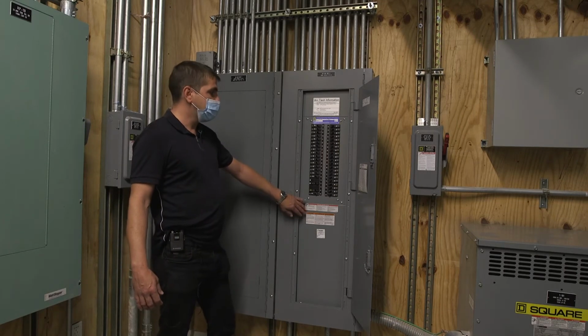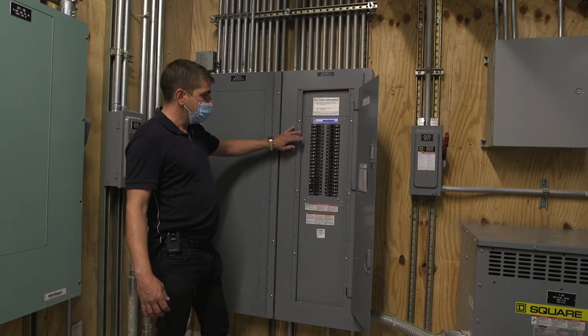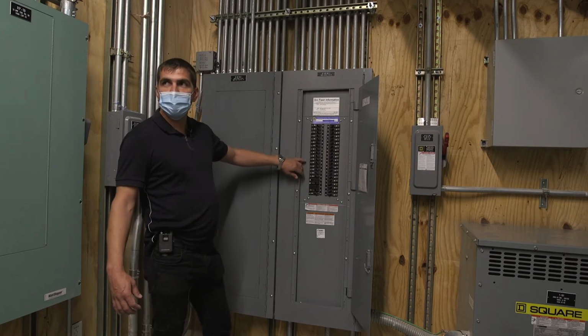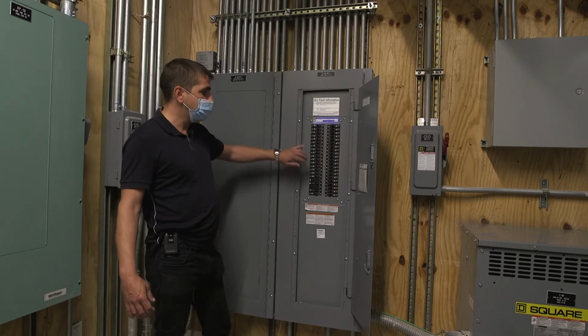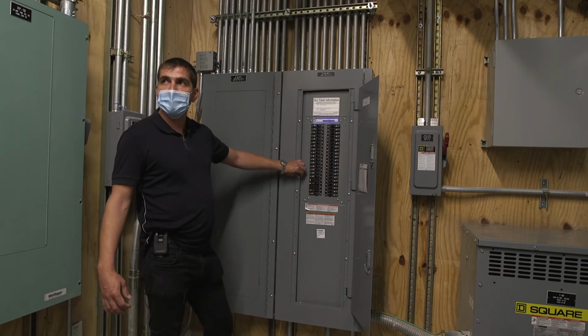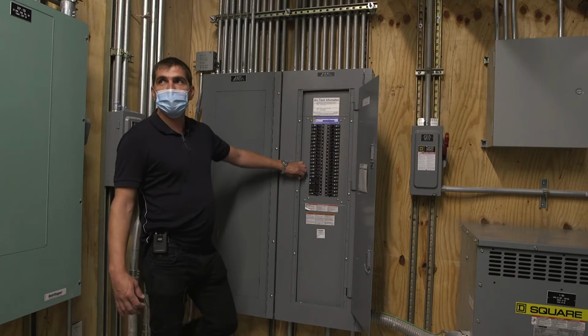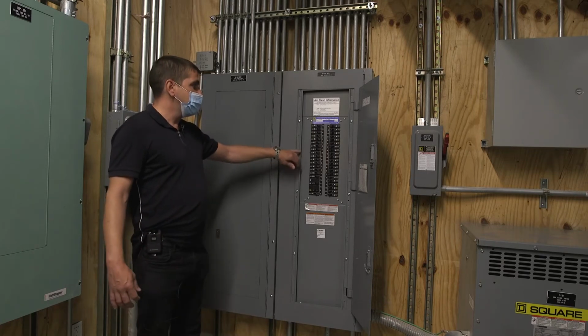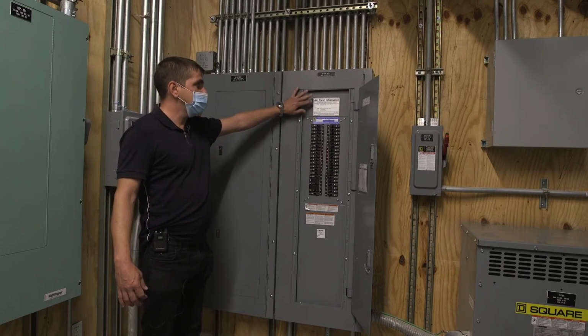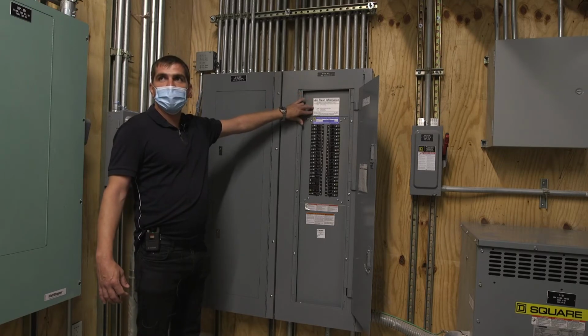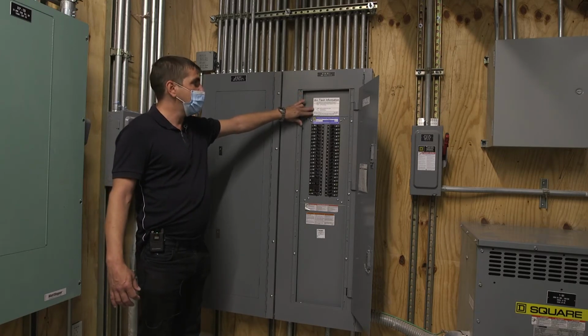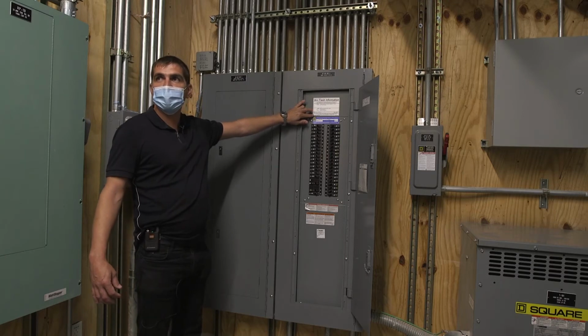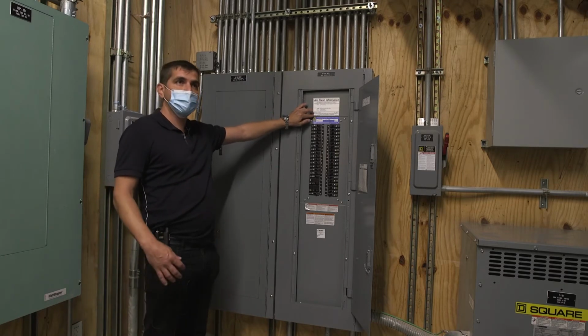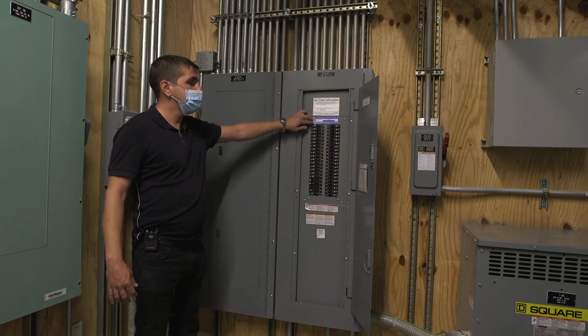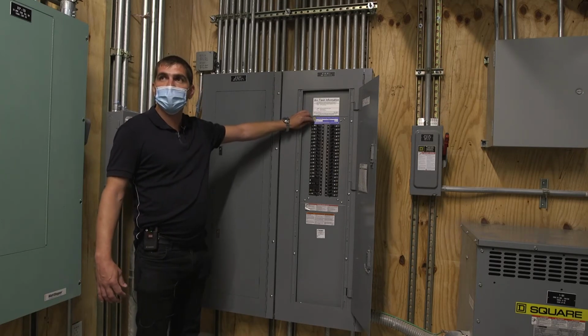So anytime something needs to be done on the panel, the best idea is to de-energize it using the upstream disconnect switch, and then service the equipment. Arc flash information is also included here. If the disconnect of power is impossible or is going to create a dangerous condition, and it has to be serviced energized, all of the safety requirements for working with arc protected equipment have to be used.